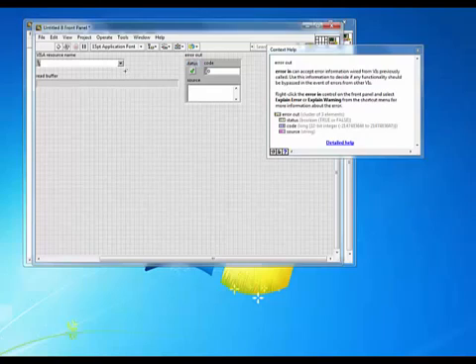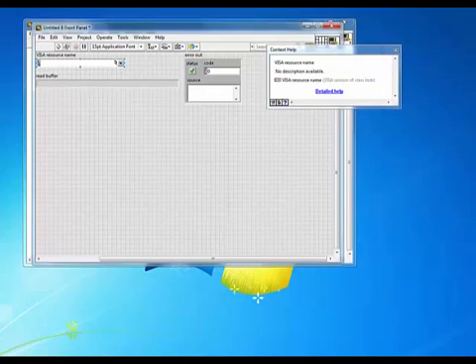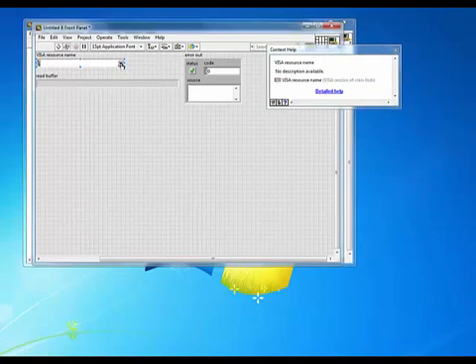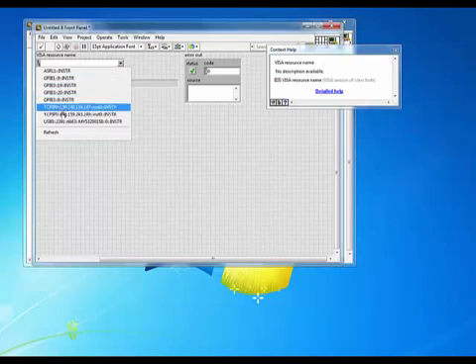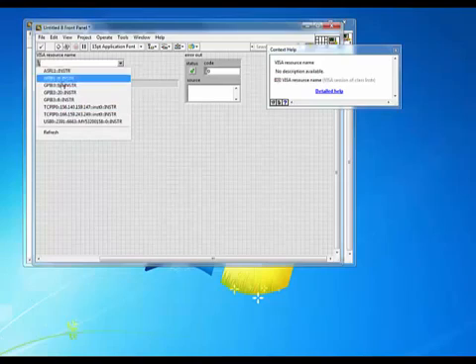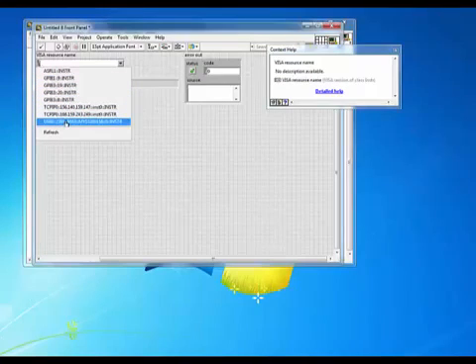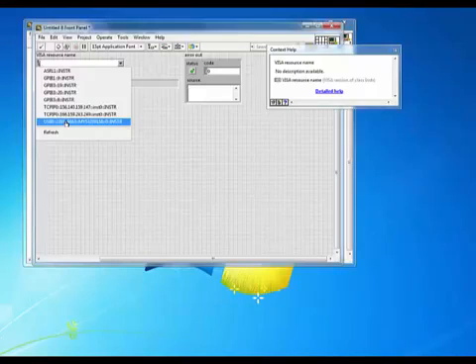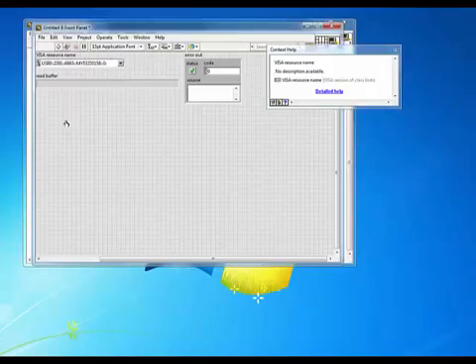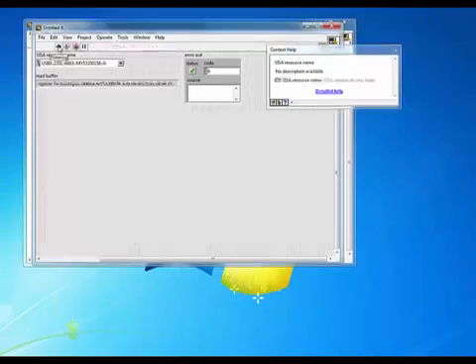All right, and so we're ready to test. First thing we want to do is select a VISA resource name. When you hit the drop down, you should see a list of any of the items that you have connected right now and have verified in the measurement and automation explorer. I'm going to choose this USB connected instrument and we'll go ahead and hit the run button.